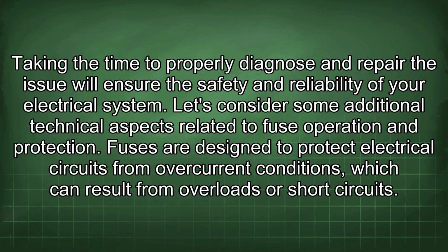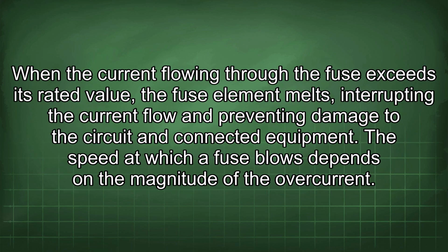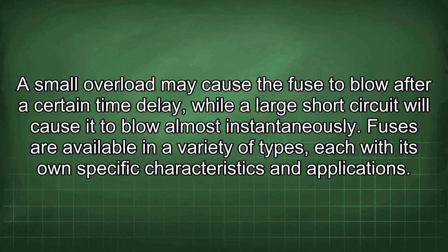Let's consider some additional technical aspects related to fuse operation and protection. Fuses are designed to protect electrical circuits from overcurrent conditions, which can result from overloads or short circuits. When the current flowing through the fuse exceeds its rated value, the fuse element melts, interrupting the current flow and preventing damage to the circuit and connected equipment. The speed at which a fuse blows depends on the magnitude of the overcurrent. A small overload may cause the fuse to blow after a certain time delay, while a large short circuit will cause it to blow almost instantaneously.